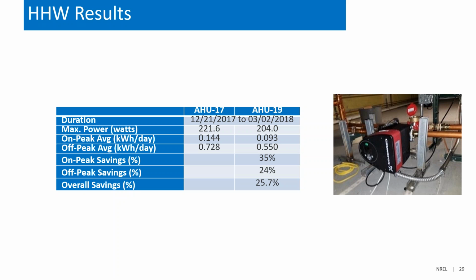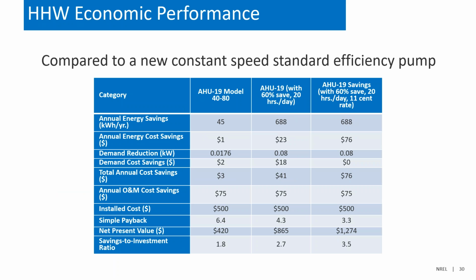So really the energy savings come from that variable speed operation. And given the fact that these pumps only turn on for about 4 or 5 hours a day, they were running at a higher percent load throughout the day. But overall, we did see about a 25.7% improvement in energy savings.